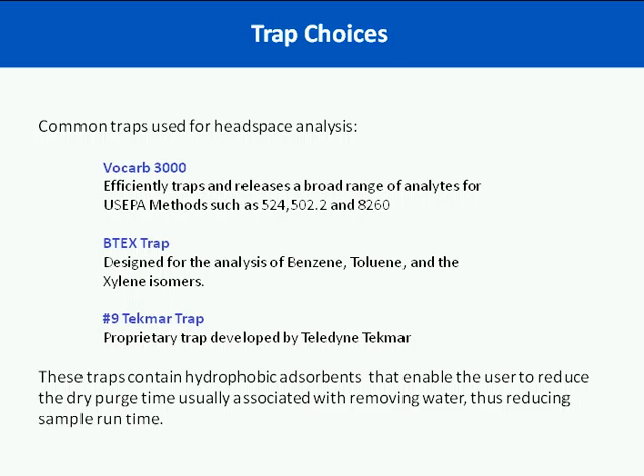As I mentioned earlier, there are many trap choices when doing dynamic headspace analysis. Some common traps used today are your Vocarb 3000, which is typically seen for Method 8260, 502, 524, 1035, etc. The BTEX trap is designed for the analysis of benzene and xylene isomers. The Number 9 is a proprietary trap by Teledyne Tekmar, designed as an improvement over the Vocarb 3000 trap. If you're having issues with water management or not good retainment of your gases and you're currently using a Vocarb 3000 trap, I would recommend moving to the Number 9 trap to see if you get better recoveries for your target analytes.